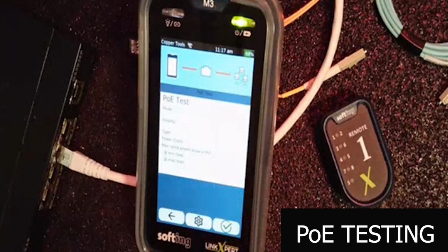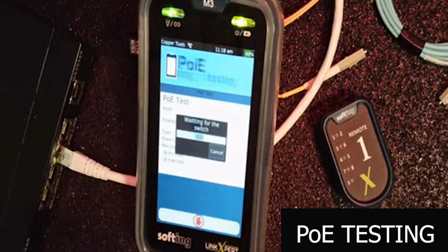So what do we do that's so special with PoE testing on LinkXpert that others don't do? Well, we actually pull a load over the cable from the power sourcing equipment. We act just like a PD, a powered device. Okay, let's go ahead and start the test.